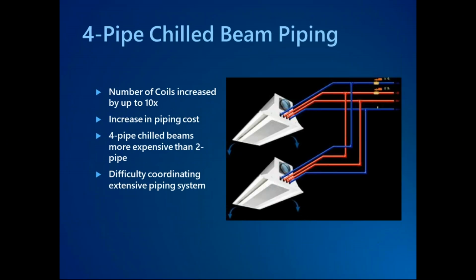So when chilled beams first came on the market, the piping idea was to take that four-pipe system with the two coils in the airstream and put those coils at every single chilled beam, at every single diffuser, more or less. And it was expensive and cumbersome. And when you think about the number of coils we're adding to a building, if a single fan coil was feeding 10 diffusers, and we had two coils in that fan coil, we now have two coils at every single diffuser. It can compound the amount of piping and the amount of coils needed pretty drastically.